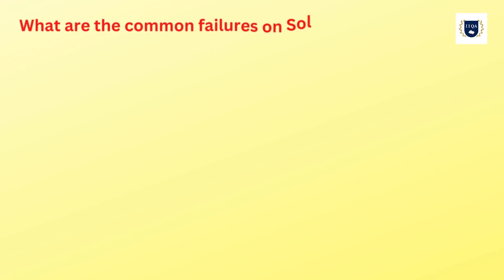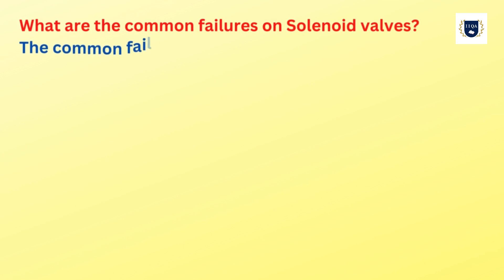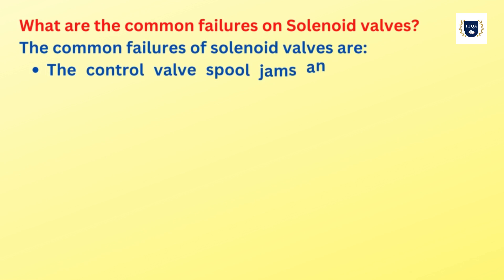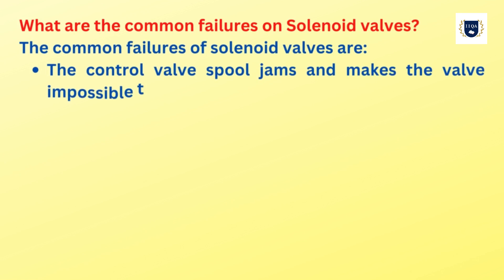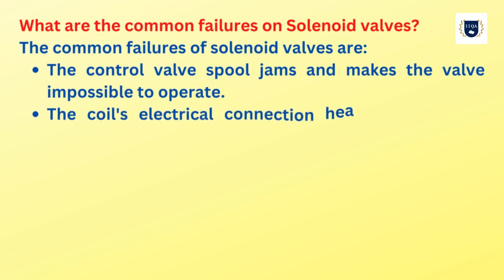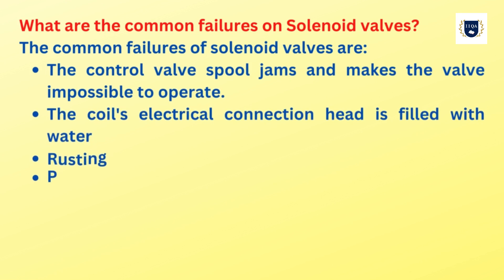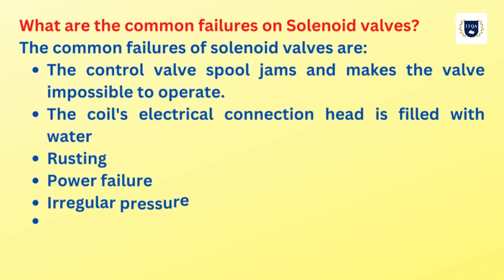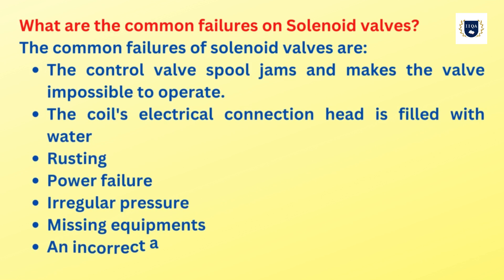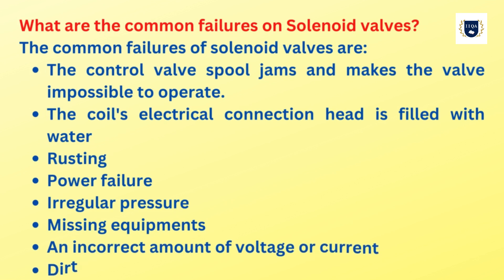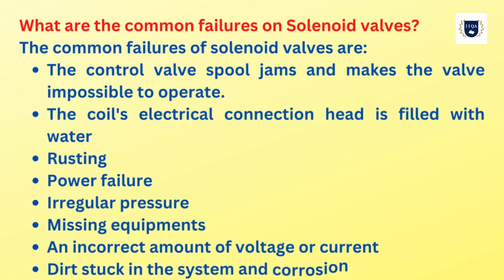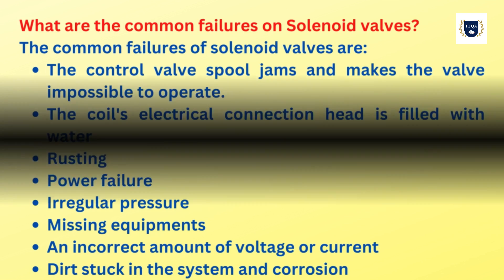What are the common failures of solenoid valves? The common failures are: the control valve spool jams and makes the valve impossible to operate; the coil's electrical connection head is filled with water or rusting; power failure; irregular pressure; missing equipment; an incorrect amount of voltage or current; dirt stuck in the system; and corrosion.